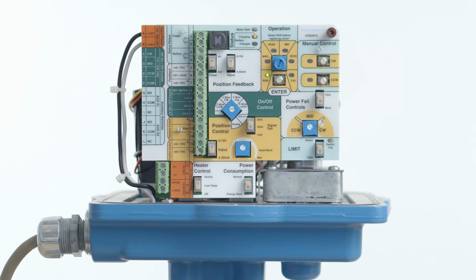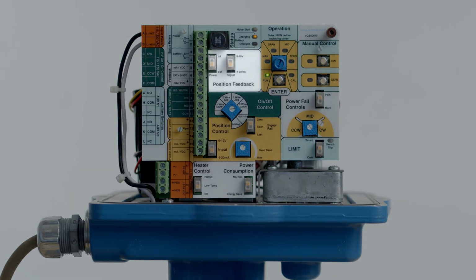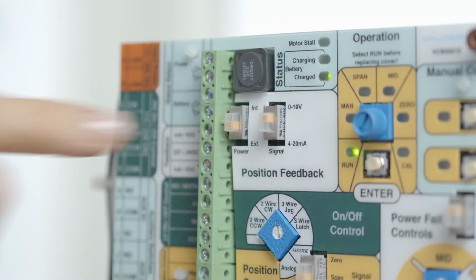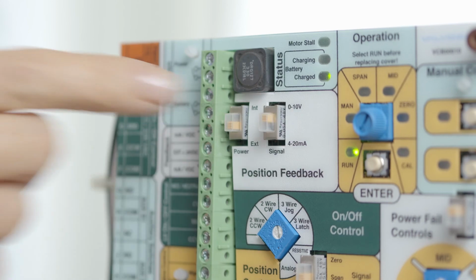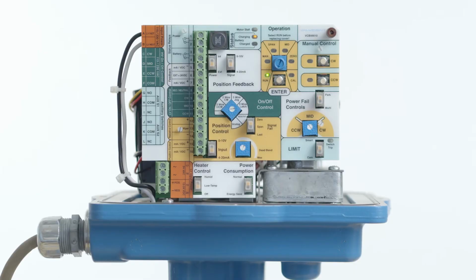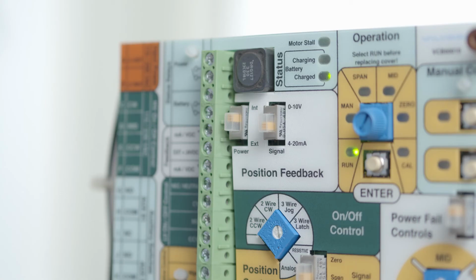As a standard feature, the unit also is equipped with position feedback. First, we'll select milliamps or voltage. Slide the selector switch down for 4 to 20 milliamps or up for 0 to 10 volts DC. The feedback signal can be generated internally or it can be loop powered. To use loop power, slide the selector down to select external mode. To use the internally generated signal, slide the selector up to select internal mode.